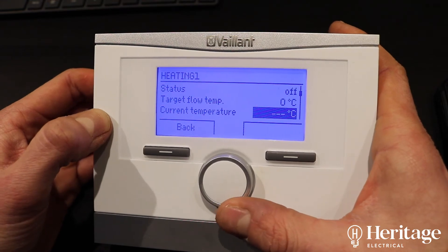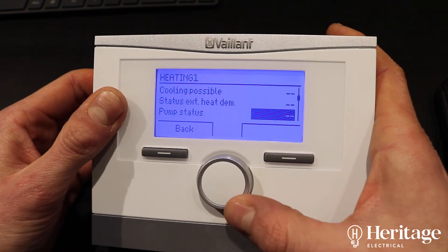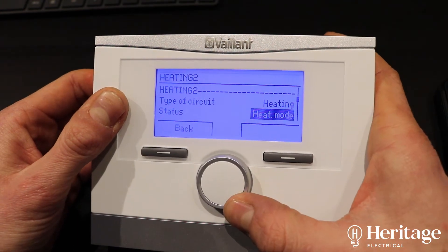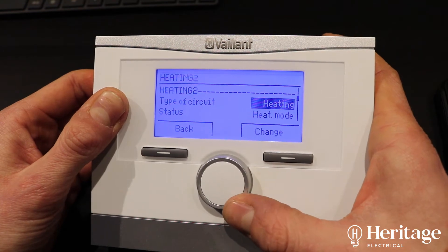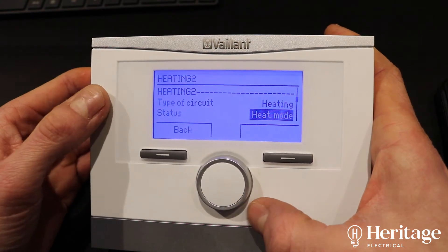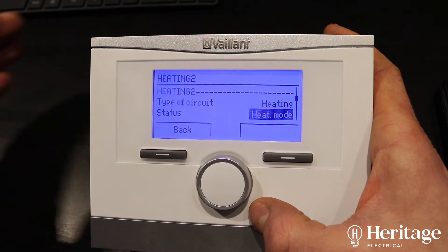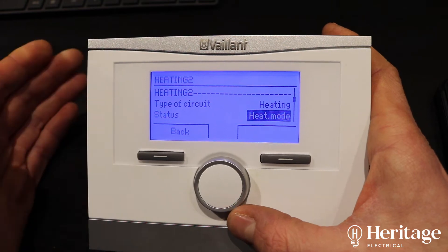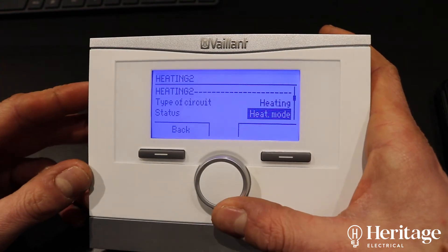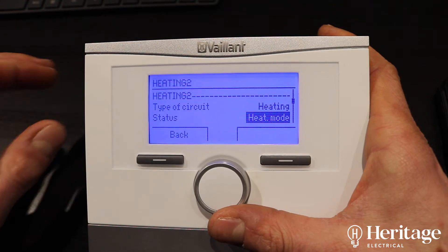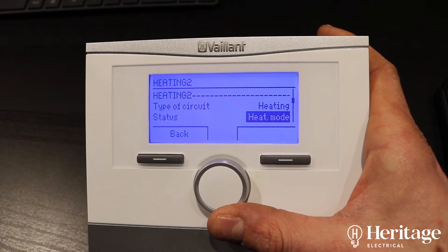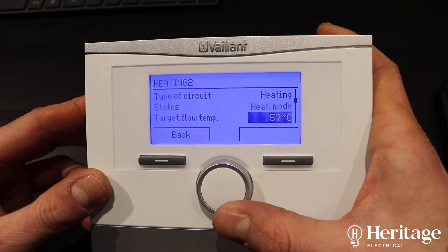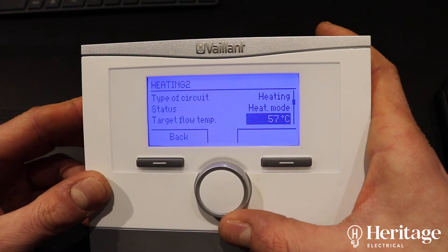If we scroll down to heating two — just give it a moment to update — again this is a heating circuit and this one is calling for heat. This relates to the second heating loop — the underfloor heating in the extension. The Heatmiser thermostats speaking with the UH8 wiring centre are calling for heat, and so the UH8 is also calling for heat. That's why the boiler is in heat mode.